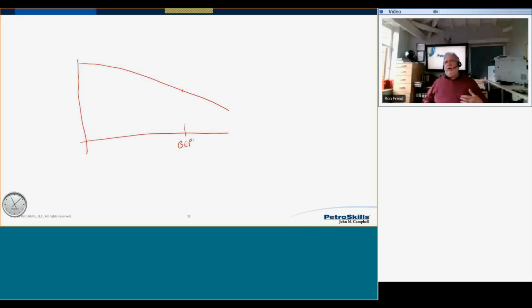So if we look at the pump curve, there's your pump curve there, and let's say that's your best efficiency point. That's where I really would like to operate. So that's my best efficiency flow. So when we do our calcs, that would be our operating point. Perfect. Lovely. Let's add 10%, shall we? Because we need 10% for the future. So we go and we're now operating there. Great. But in reality, our pump's oversized. So we're actually operating down here somewhere on this pump curve, because we've got a bigger size pump.